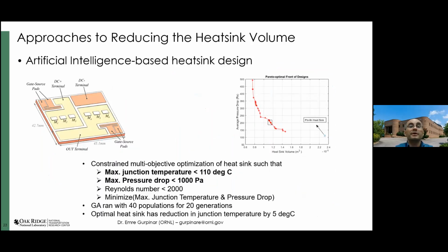I think it should still be available if you're interested in the details. With this, we have two objectives: keeping the highest junction temperature, for example with six die, below 110 degrees C, and keeping the maximum pressure drop below 1,000 pascals.